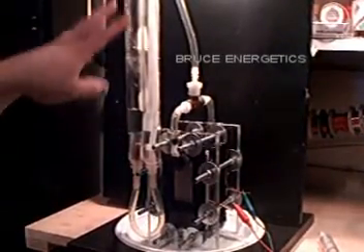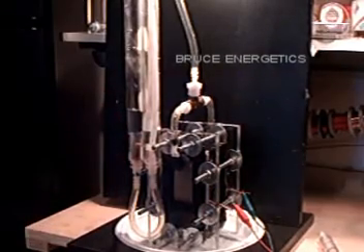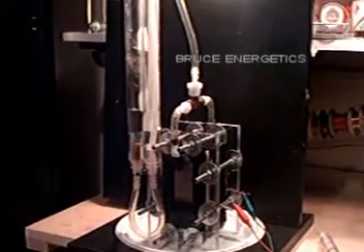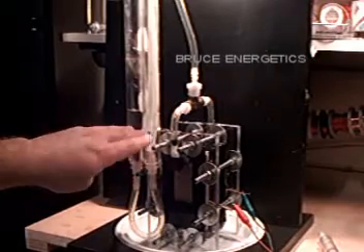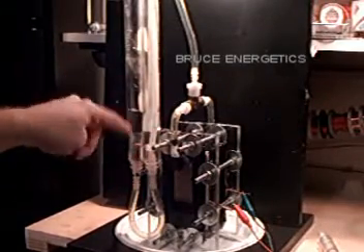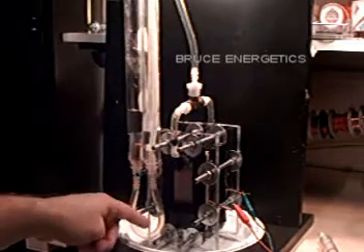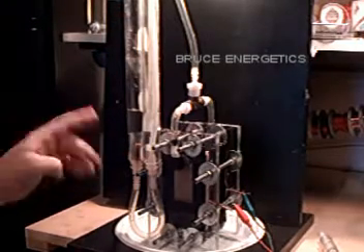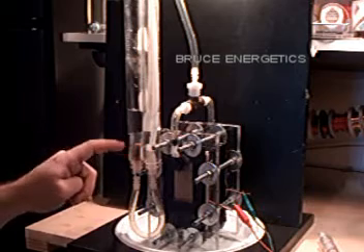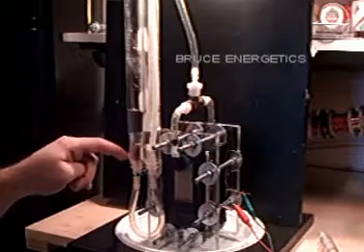I cleaned out and flushed this bubbler and scrubber combination. It flushed out all the gook that got caught in there, so now we shouldn't have the problem of the foam adding to the water volume in the neutralizer column before it gets to the standard bubbler on this side. Hopefully this thing won't rust as much as I suspect it's rusting — I could probably just put a little seal around the bottom of it to avoid that.